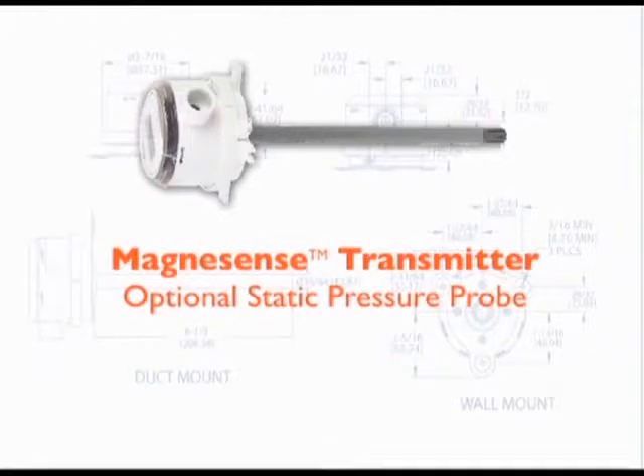Dwyer Instruments Incorporated offers an option on the Magnesense transmitter that will simplify installation in this duct static pressure application. An inherent static pressure probe can be selected at the time of order that will alleviate the need of using tubing and static pressure sensors. The elimination of these parts will dramatically simplify and reduce installation time. To mount the Magnesense transmitter with the inherent static pressure probe, simply drill a 0.5 inch or 12.7 millimeter diameter hole into the duct.